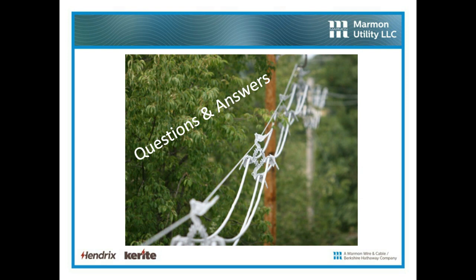Okay, great, thanks. Next question, is there any concern with insulation degrading over time due to abrasion of the tree contact and possibly resulting in energized trees? Yes and no. So first, let's go to the first part of that. We're allowing intermittent contact between leaves and the spacer cable system for the life of the system. So I have leaves or wet leaves slapping against the conductor. That's no big deal. If I start having tree branches that might have a 3, 4, 5-inch diameter and they have some heft or some weight to them and they're rubbing continuously against that insulation, then yes, there will eventually be abrasion. There's no other result to be expected than abrasion.